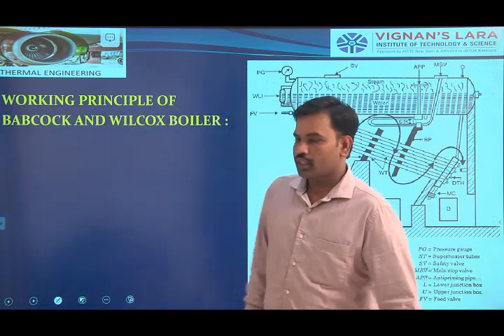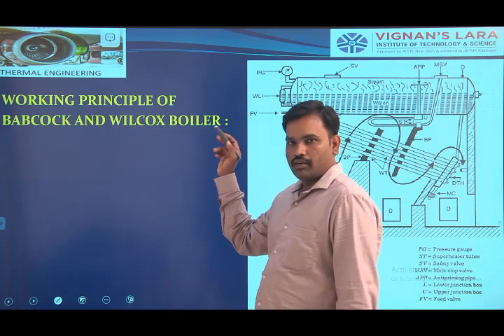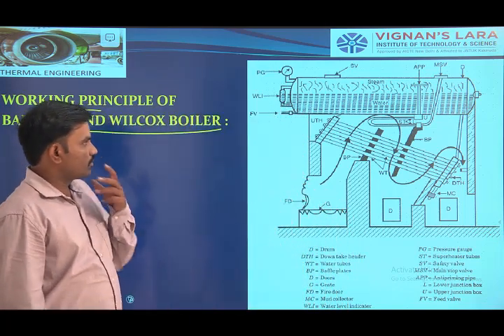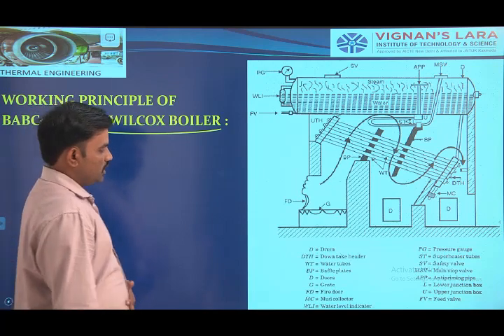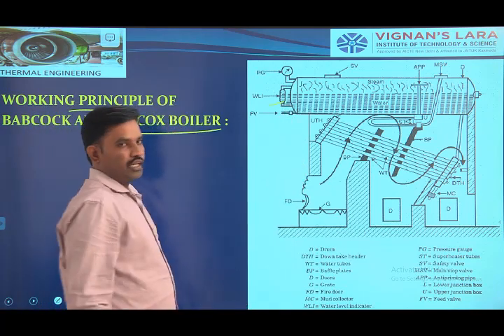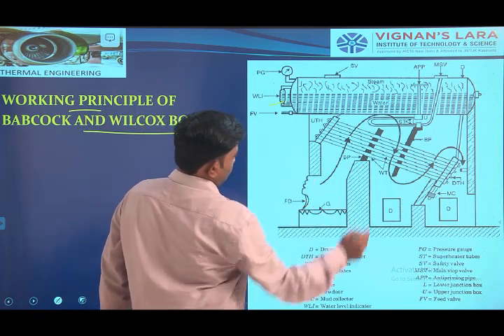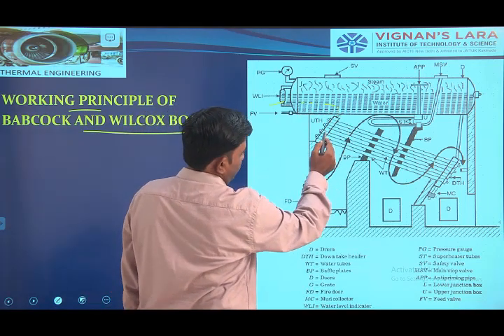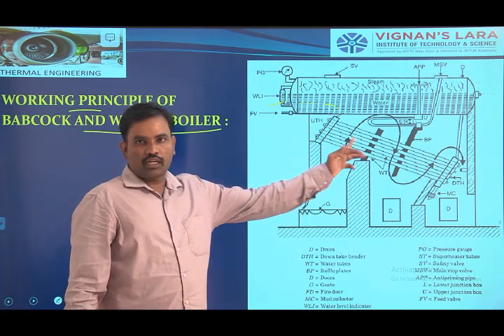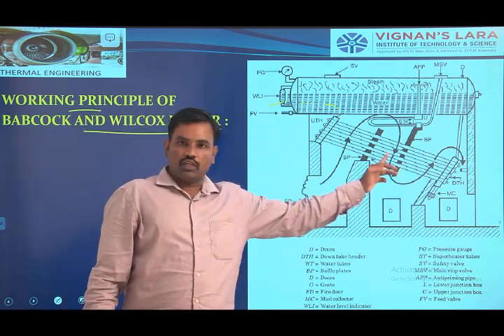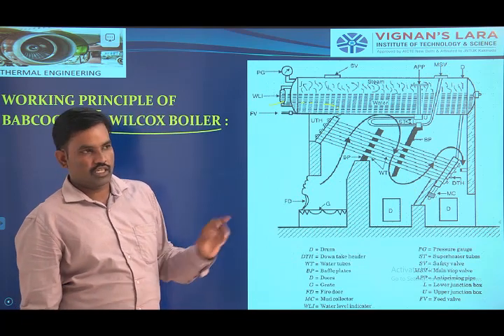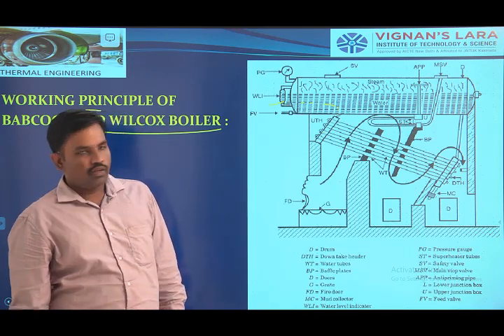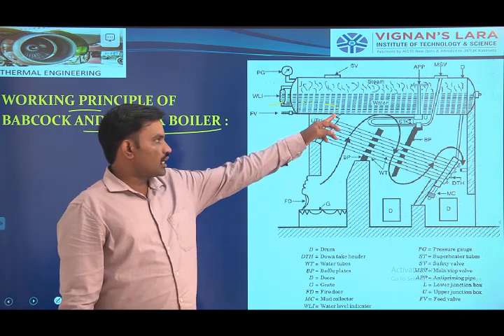See the next type of boiler — the Babcock and Wilcox boiler. Here we can see the diagram. This is the boiler drum, and we are arranging the boiler tubes inclinedly. From the boiler drum, water flows from the upper header to the lower header. Here we are arranging the tubes inclinedly, and because of gravitational force only, water is circulated naturally. It is also a natural circulation type of boiler. The hot flue gases flow over the tubes, and water flows inside the tubes — that means it is a water tube boiler, a natural circulation type of water tube boiler.